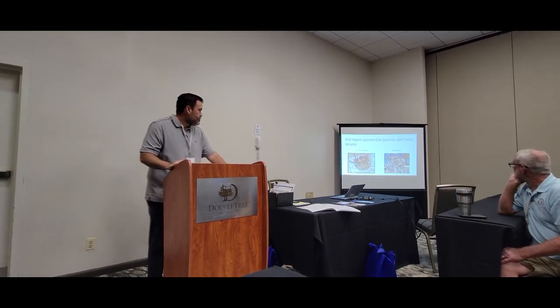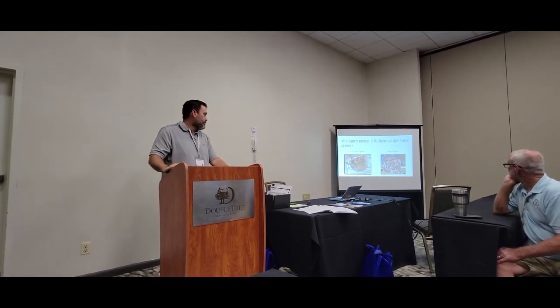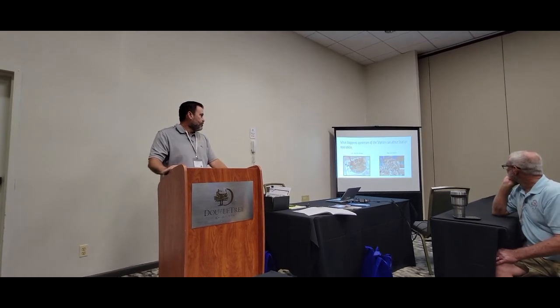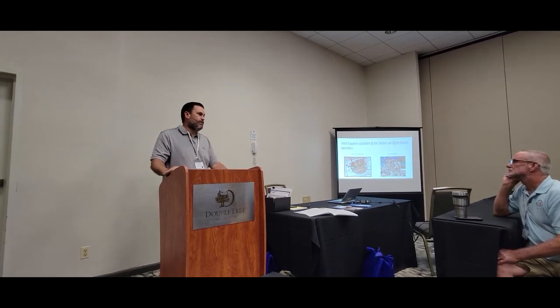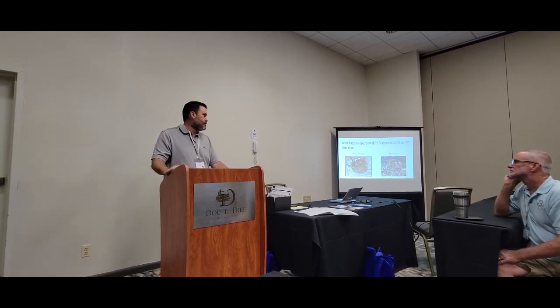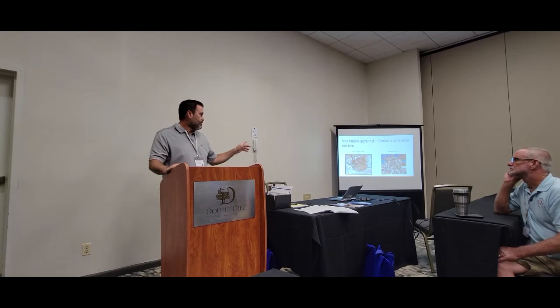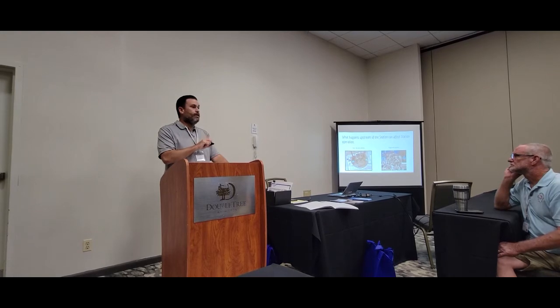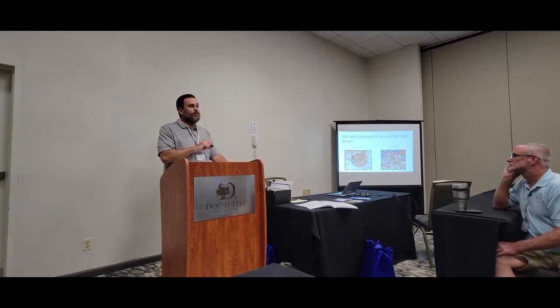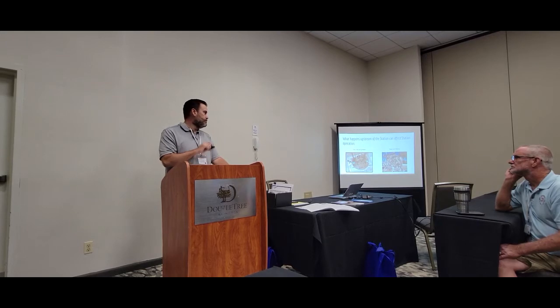So this is a picture of this lift station. Lift station on the left has a bunch of grease in it. Lift station on the right has a bunch of rags. Both of those are problems because they will clog up the lift station, and grease, nobody wants that in their wastewater treatment plant. It messes up the bugs. And that's why you want to clean it on a regular maintenance, to prevent backups, especially prisons, apartment complexes, hospitals. They're gonna have a big problem with rags if they don't every 1 to 3 months clean the lift station.